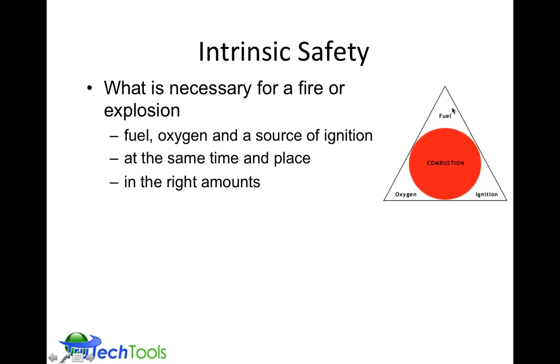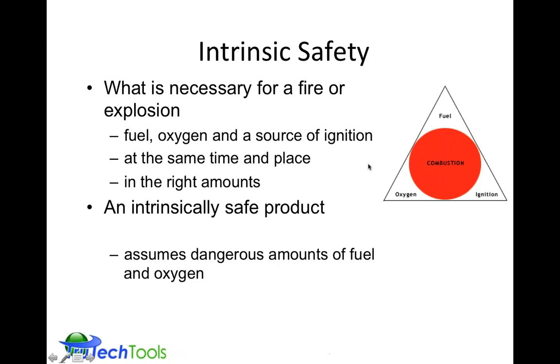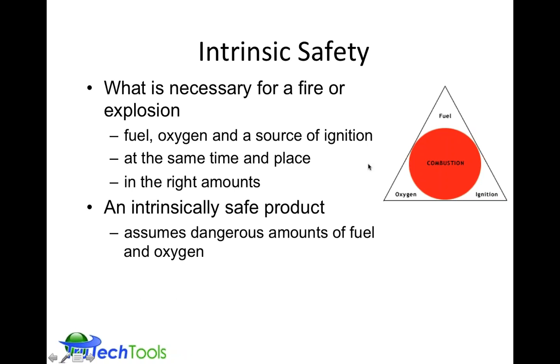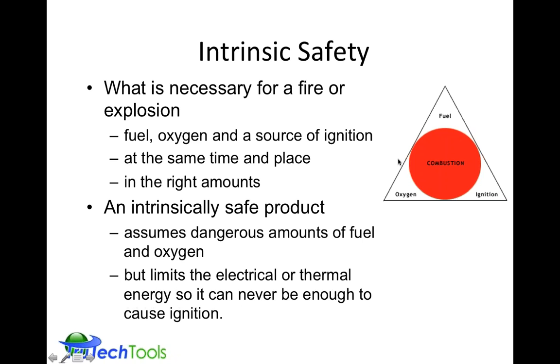And it's your environment where you have the fuel and the oxygen going on. And we'll be talking more about oxygen concentration measurement and fuel concentration measurement, and you'll see how all of this fits together in terms of explosive protection. So an intrinsically safe product assumes that there's a dangerous amount of fuel and oxygen, a dangerous mixture, and we'll talk about what those mixture levels are in a few minutes. And the intrinsically safe product will limit the amount of ignition energy so it can never cause an ignition. So it's assuming things are bad out there in the world, but it's never going to introduce any kind of power that could cause this ignition to happen.